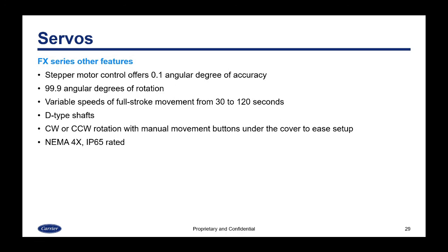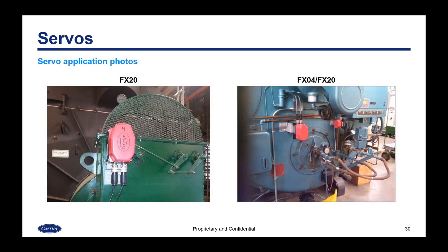Some other features of the FX series servos are that they have stepper motor control with 0.1 angular degrees of accuracy, meaning that over the 99.9 angular degrees of rotation that are available, you get 999 positions. Variable speeds of full stroke movement can be set in the control from 30 to 120 seconds. It comes with a D-type shaft for mounting to couplers. You can have clockwise or counterclockwise rotation with manual movement buttons provided under the cover to ease setup. And the servos are all NEMA 4 or IP65 rated. Here are some images of the servos in application.